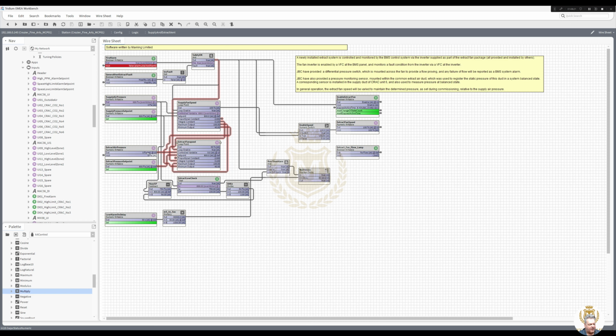I want to monitor change on any of these sensors, because I don't know at the moment. I'm not on site. I don't know what the sensors are reading when the fan isn't running, and I don't know what they're reading when they are running. But what I want to do is prove flow, and the only way to prove flow is looking at what the static pressure is and what the flow pressure is, with the AND gate as well, I presume.